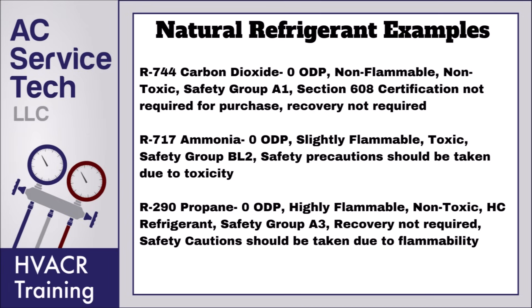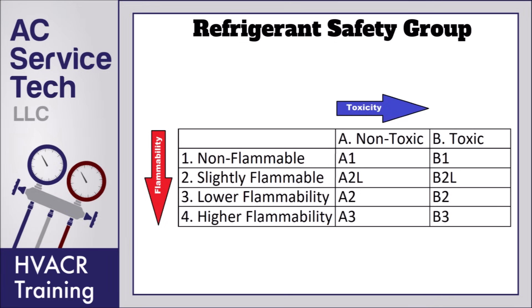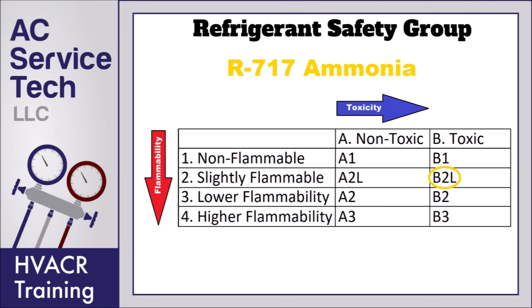This restricts where R290 can be installed. On the refrigerant safety group chart, moving to the right shows A is non-toxic and B is toxic. Moving down shows: 1 is non-flammable, 2 is slightly flammable, 3 is lower flammability, and 4 is higher flammability. R290 is non-toxic but highly flammable, which is why it has a safety group of A3. Ammonia is toxic and slightly flammable, which is why it has a B2L rating.